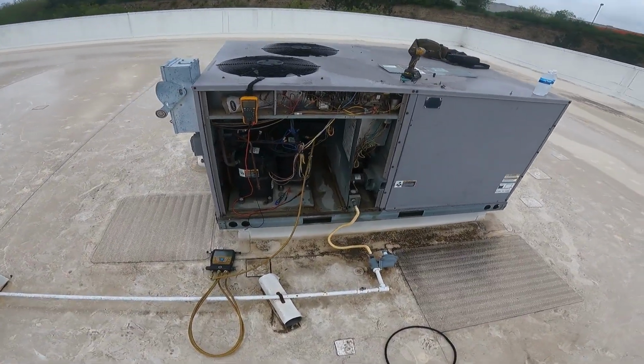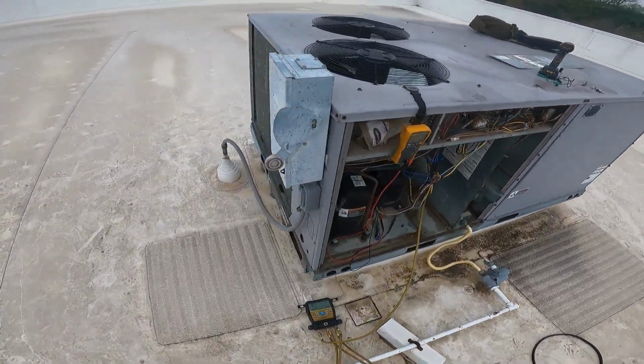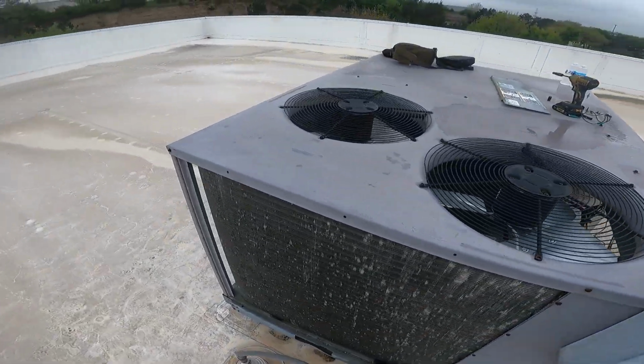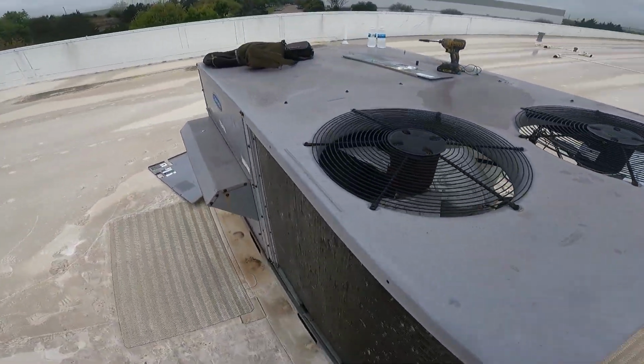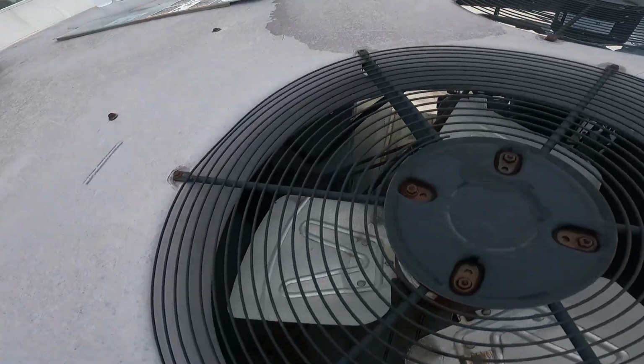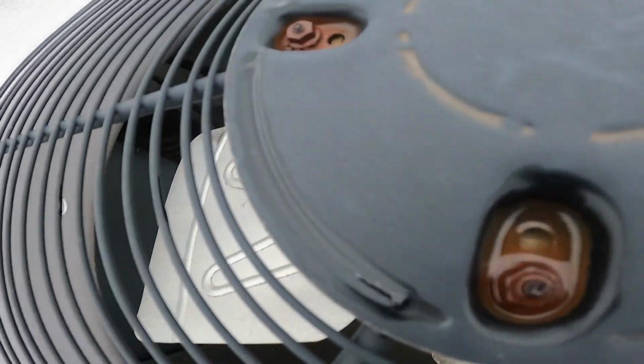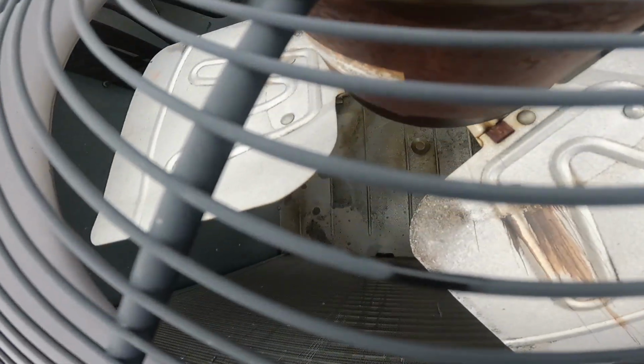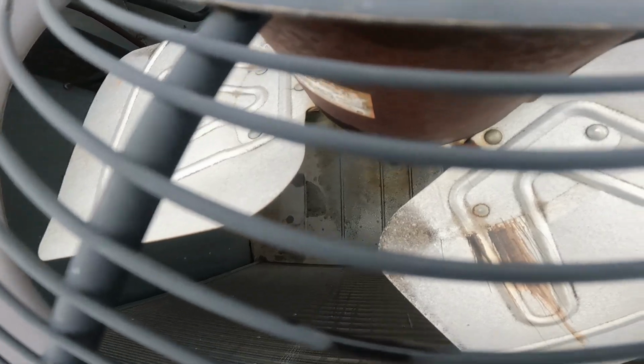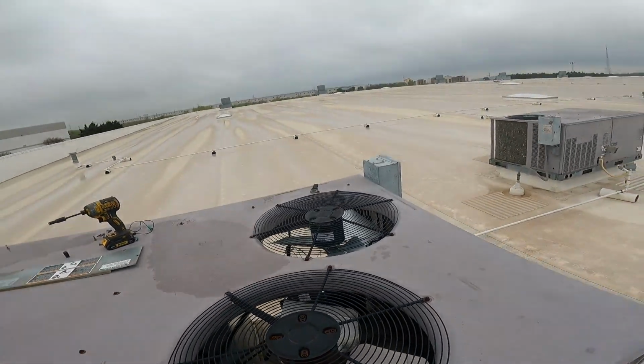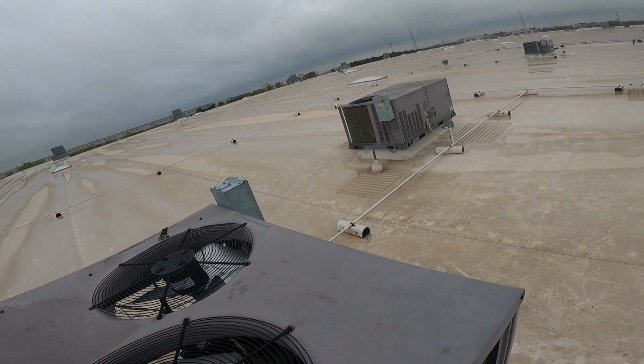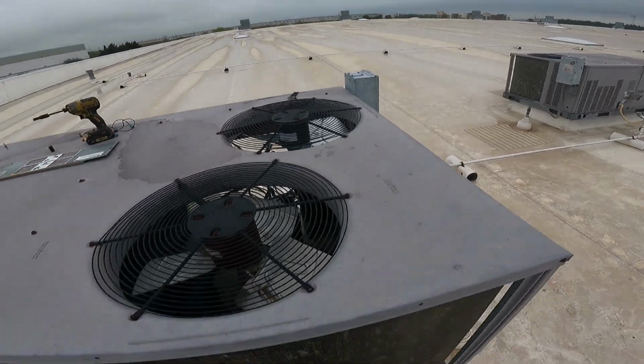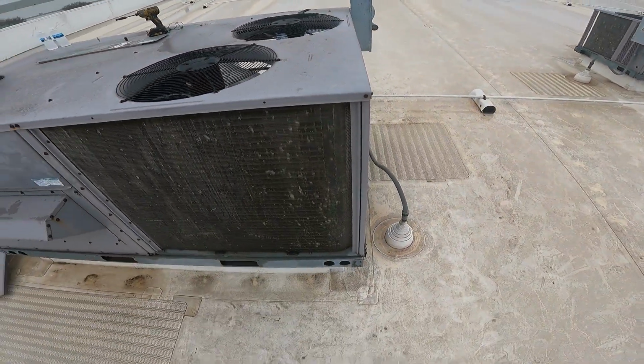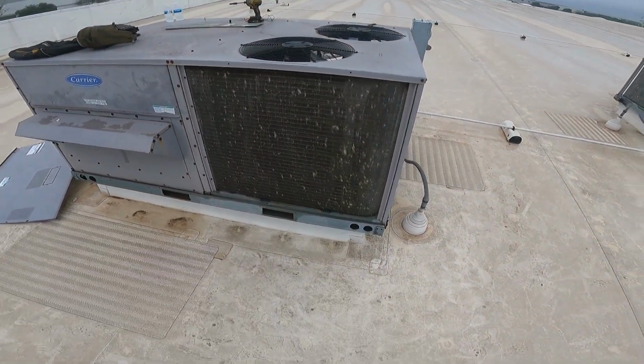That should be it. Both compressors are actually running and they're ohming out right. And when it comes to a leak check, we say leak check and possible repair. Now this is one of those things where we could do all this work and find the leak is, say, in the coil. You can still repair a leak in a coil, especially on R22 units, since they don't run off enormous pressure.